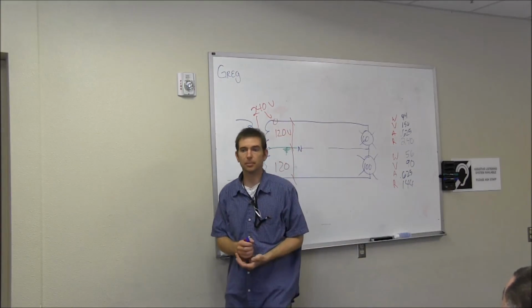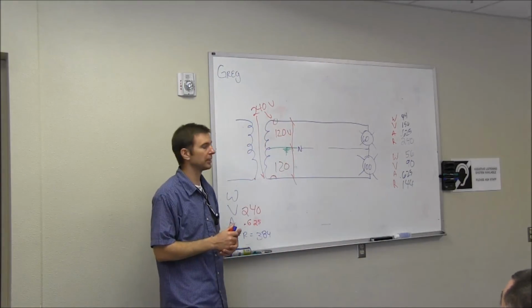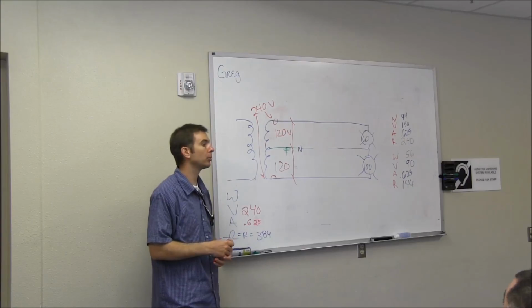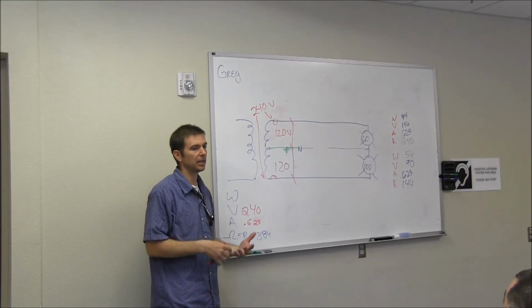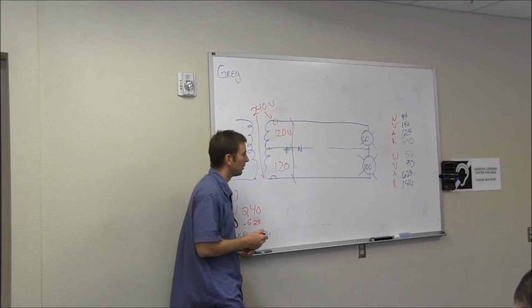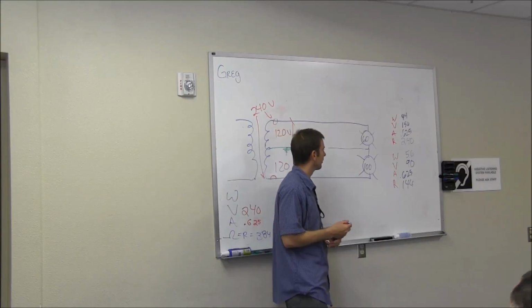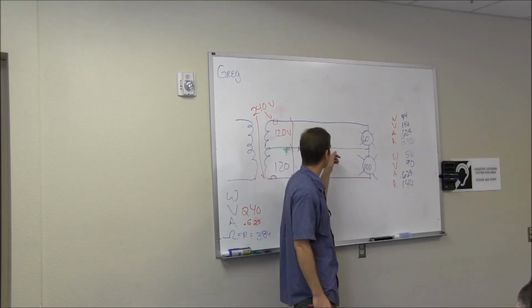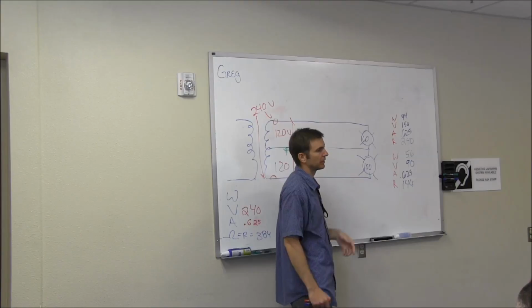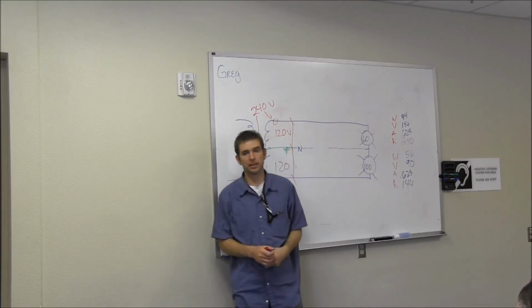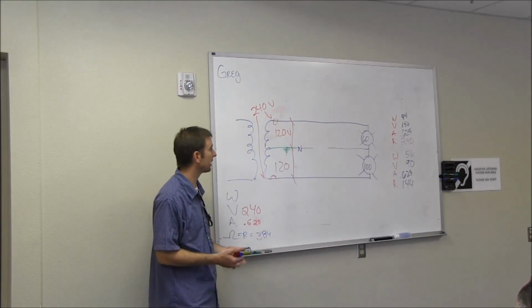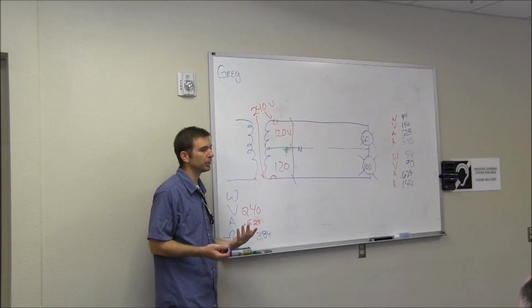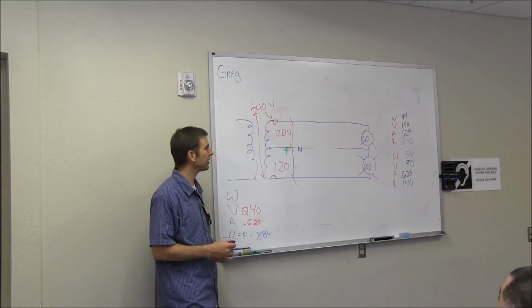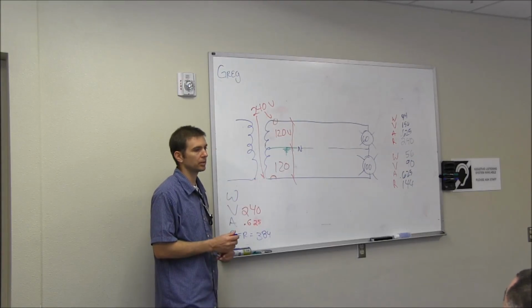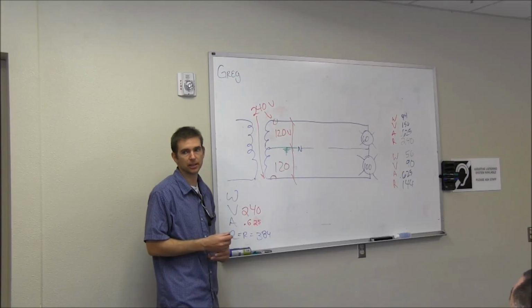So this is something you need to be really careful about when working on electrical systems. If you're working on something hot because it needs to be hot, with your PPE on and your tools for hot work, you need to make sure you don't open up the neutral on a multi-wire branch circuit, because you're likely going to fry something. We don't even use incandescent light bulbs anymore - everything you use is going to get cooked. Everything has electronics now.